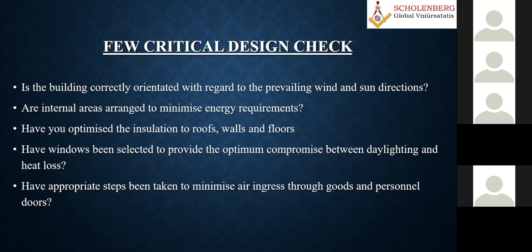Have you done all these calculations for the insulation material, selecting the heat transfer coefficient? So what type of air conditioned area, shading factors, walls, the floors, even doors, and what type of windows mechanism they have, and because you have so much infiltrated load. So this all in the checklist you must develop based on your local code.